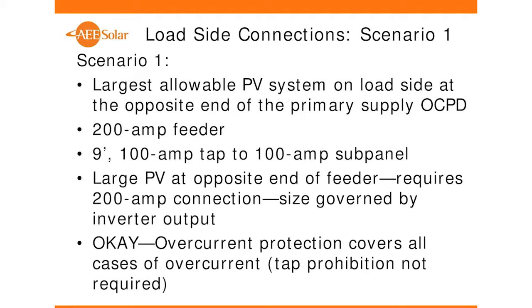So the largest allowable PV system on the load side of a 1,000 amp service. So we're going to use a 1,000 amp service. We've got a 200 amp feeder. We're going to have a 9-foot tap with 100 amp. It's got a 100 amp tap to a 100 amp panel. The largest PV system, 200 amp connection, size governed by the inverter output. Is this okay?